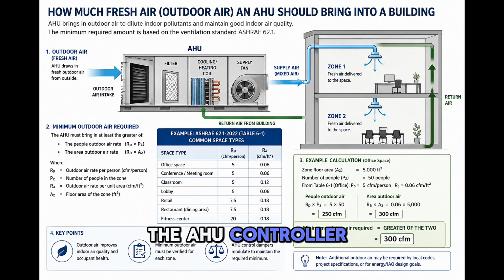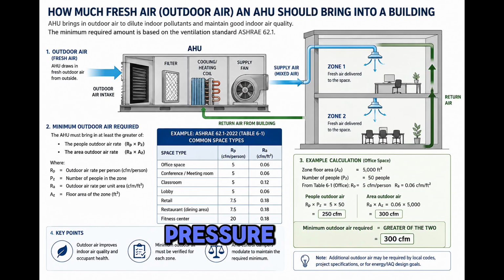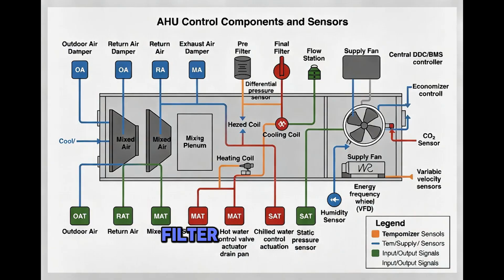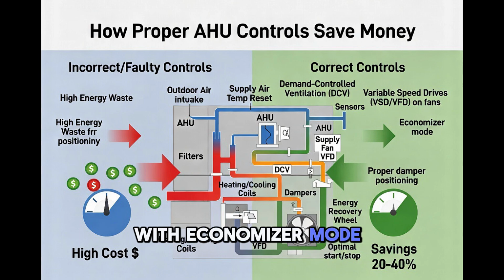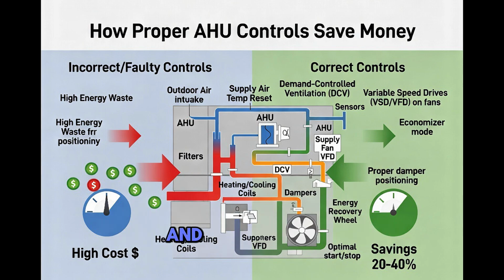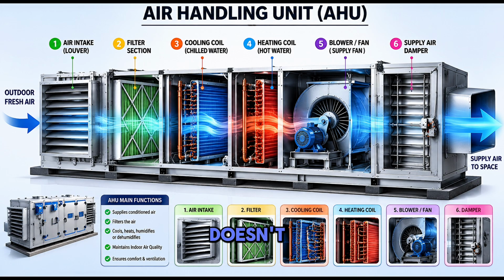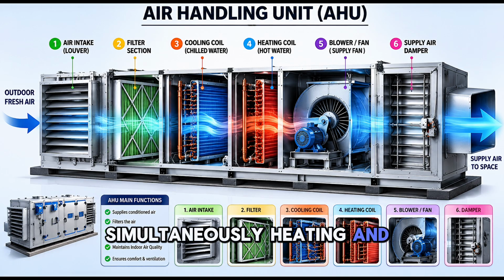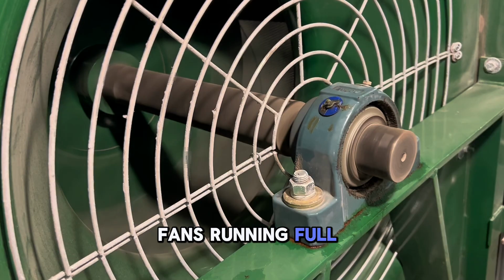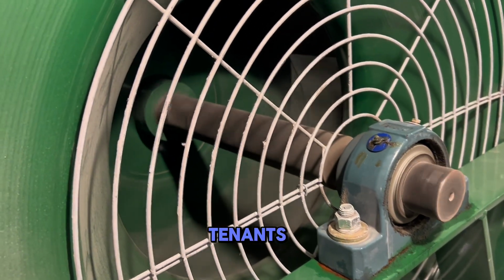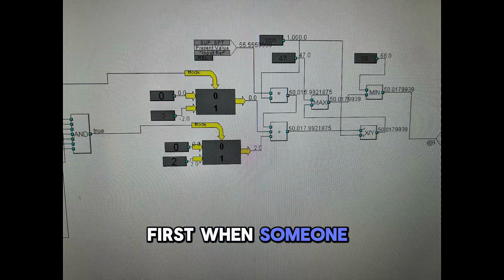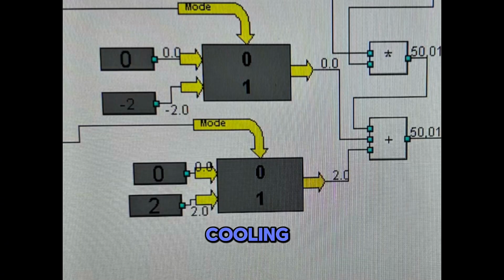Here's where building automation shines. The AHU controller is watching temperature, pressure, CO2, filter status, and more, all at once. When everything works together, you get free cooling with economizer mode, perfect supply air temperature, and low energy use. When it doesn't, you get simultaneous heating and cooling, fans running full speed for no reason, and angry tenants. Later I'll give you my top 3 things to check first when someone calls and says the building isn't cooling.